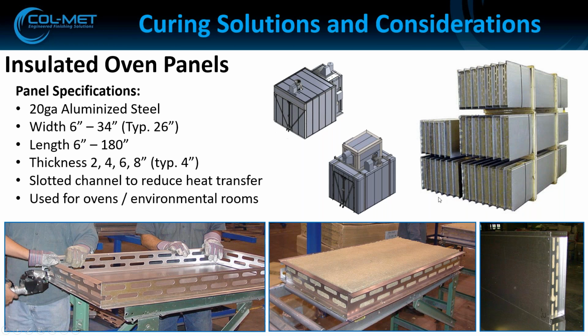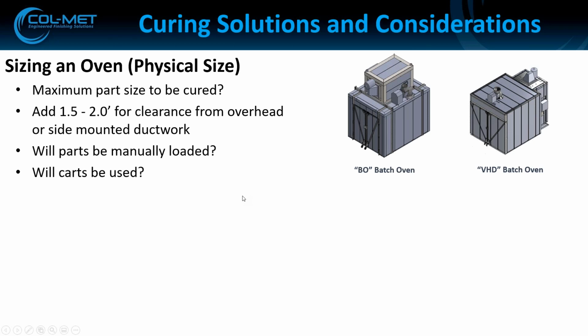When we talk about sizing an oven, the first thing you need to know is what's the maximum part size you're going to be curing. Our recommendation is that you add 1.5 to 2 feet of clearance around the sides and above the product. You also need to take into consideration how the parts or carts are going to be moved in and out and whether you might need additional space.